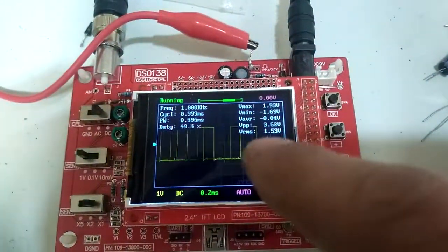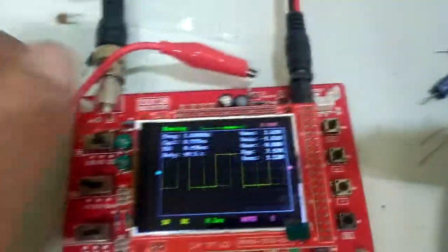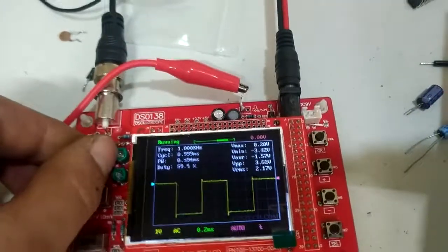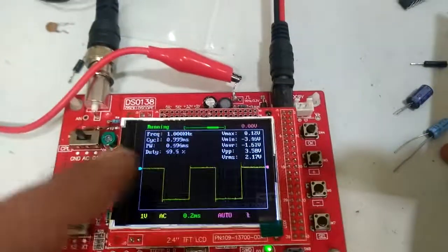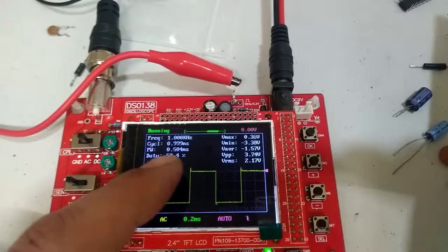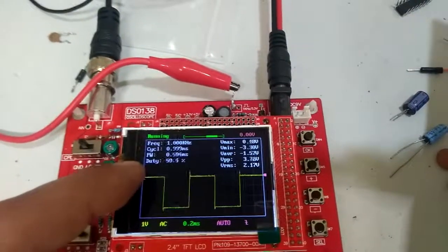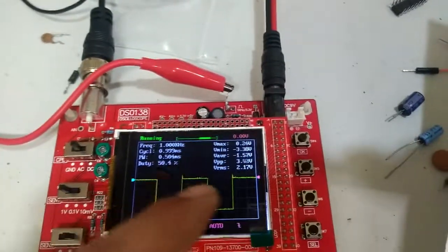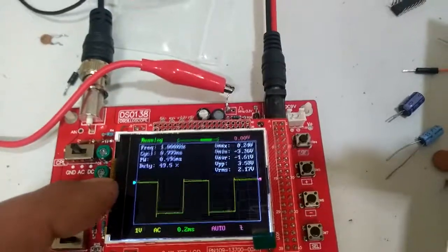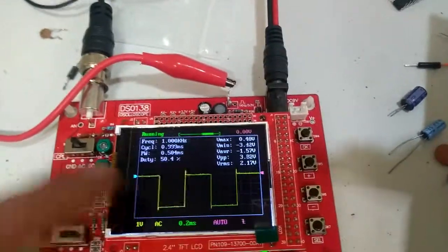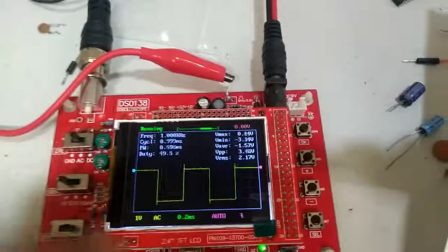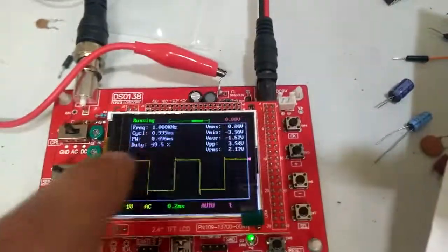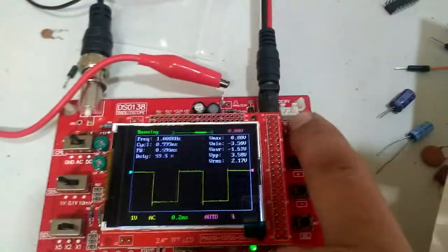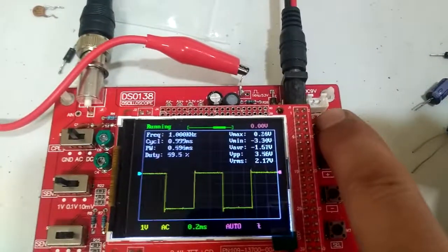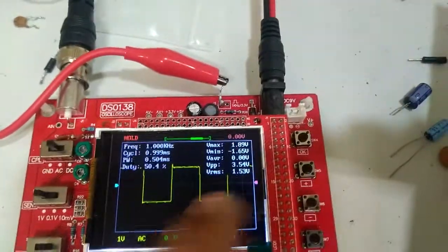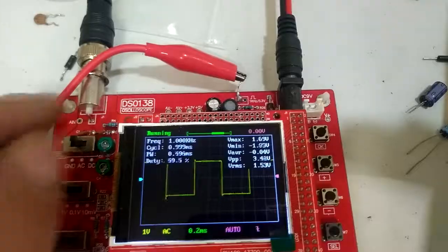That's not what I want, because this is in DC. That's kind of what I want to be showing in AC, which when I switch over to AC, now you can see it's moved the peak of the positive end of the square to the 0 volt point. So now it almost looks like what I'm looking at here is a pulse DC that's all negative square wave, and that's not what I want. So with this highlighted, just hold the OK button again for 2 seconds. And now it's calibrated that back to where it's supposed to be.